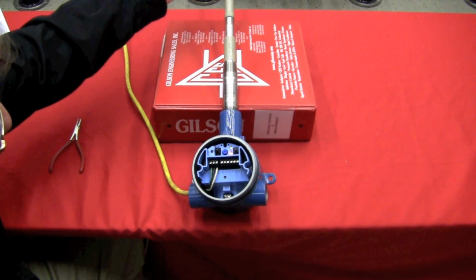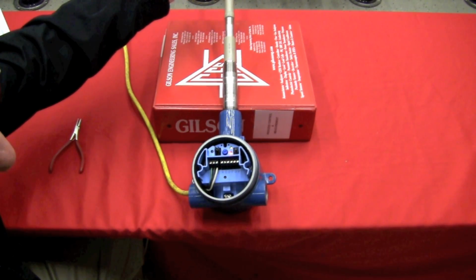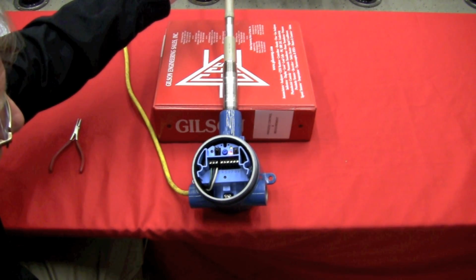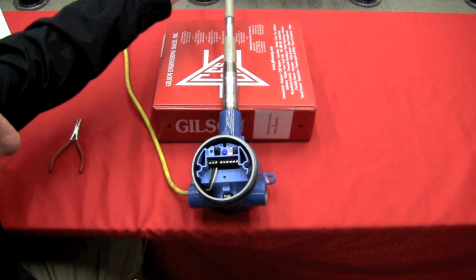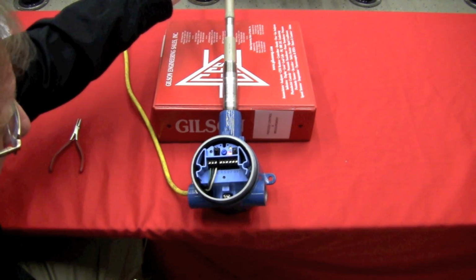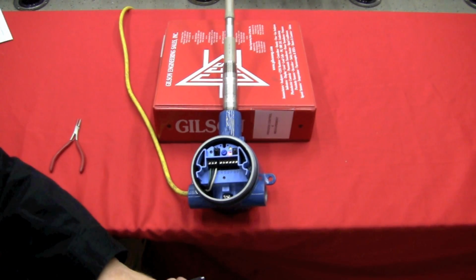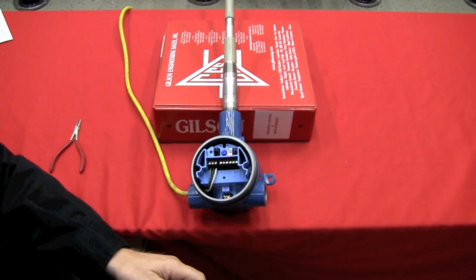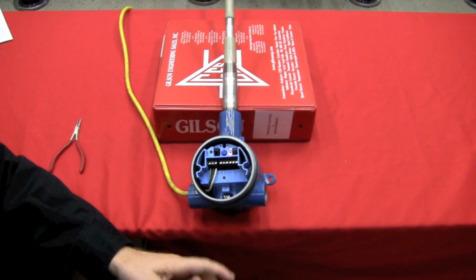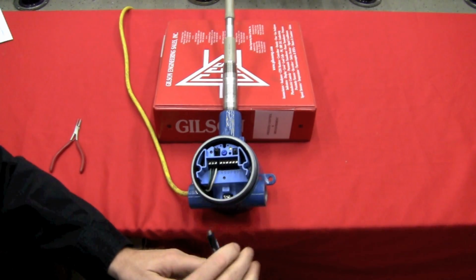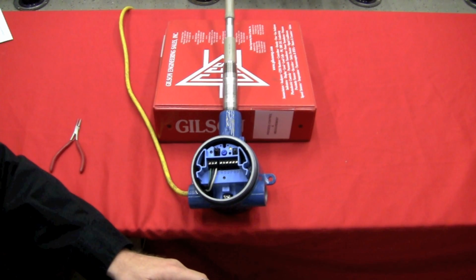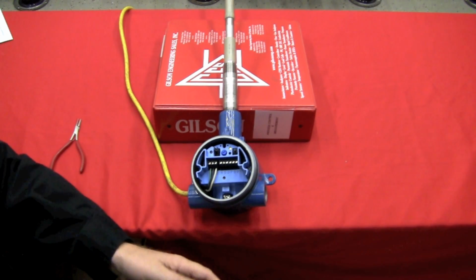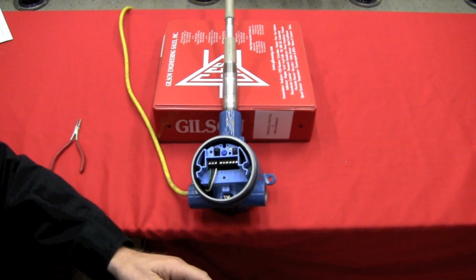Now I'll grab the probe and you'll see it goes into alarm. Now I'm going to release the probe and you'll see the red light stay lit probably for about 5 to 8 seconds because I dialed in the time delay, and then it'll come out of alarm. So my hand is off the probe and you see that we're still in alarm, and basically what that means in practice is the level would have to come back under the probe for that X amount of time, whatever you dial in there, and then the alarm will clear.